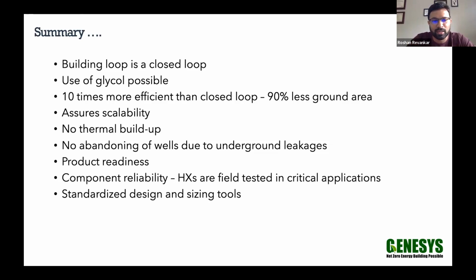One of the neat things about CLAD is the entire assembly can be pulled out of the borehole and replaced if the pump fails. So there is no need to abandon wells if there were any underground leakages. This might be the first ground source product that can actually be installed in the ground and taken out of the ground. That seems to attract some of the finance folks as seeing this as an asset now that can be installed and removed from the ground, unlike typical closed loop systems, which once it's in the ground and grouted, it just stays there.